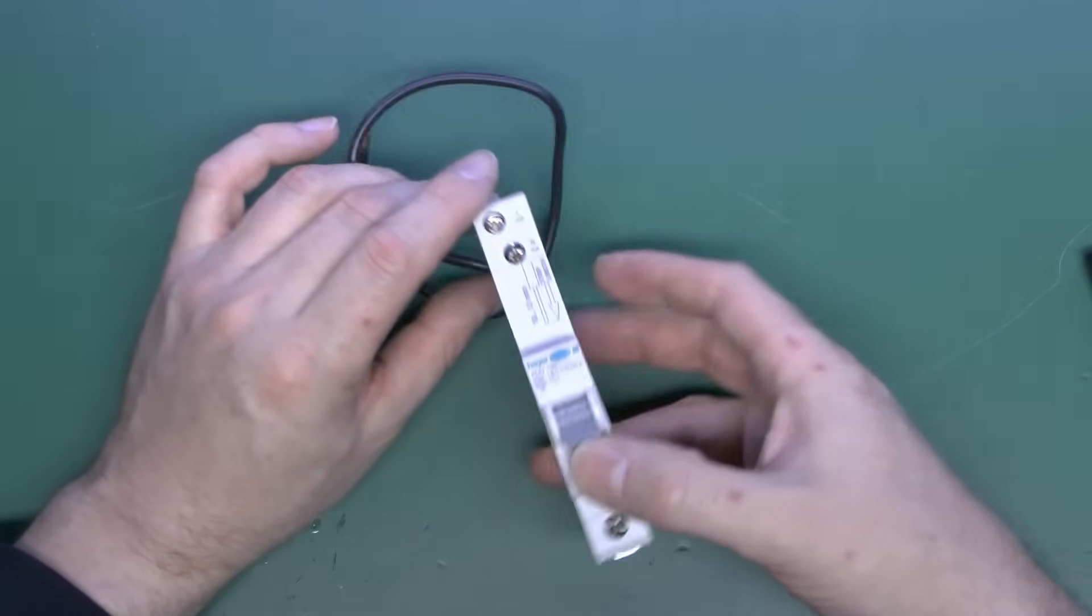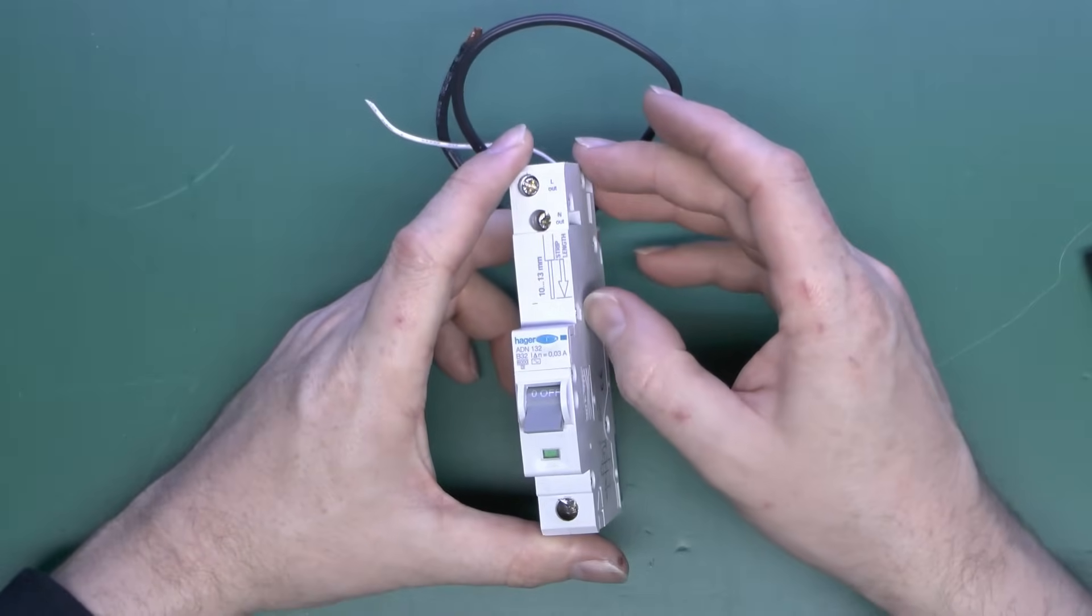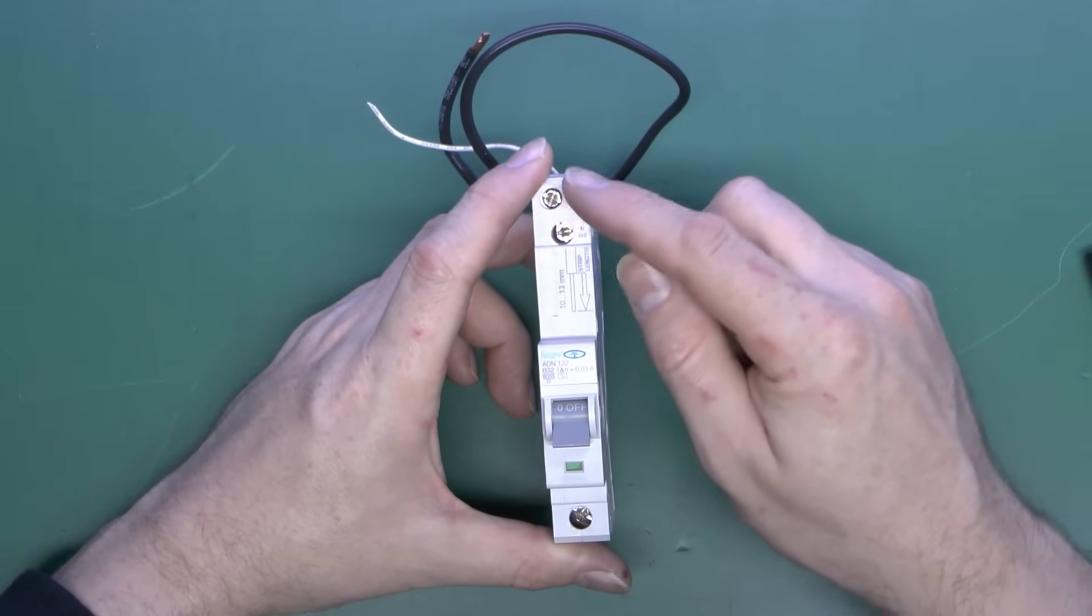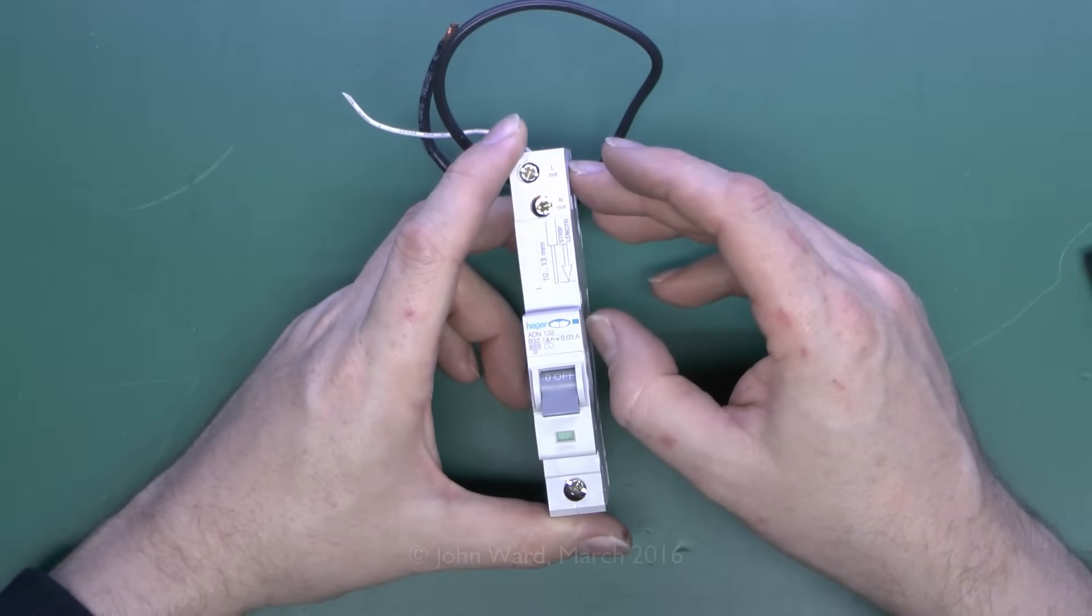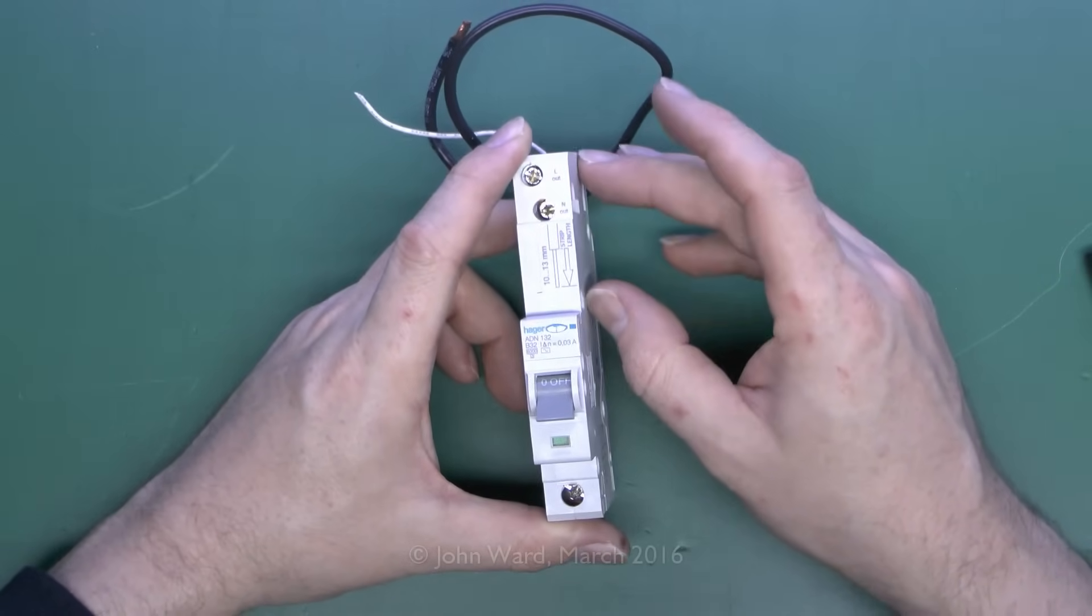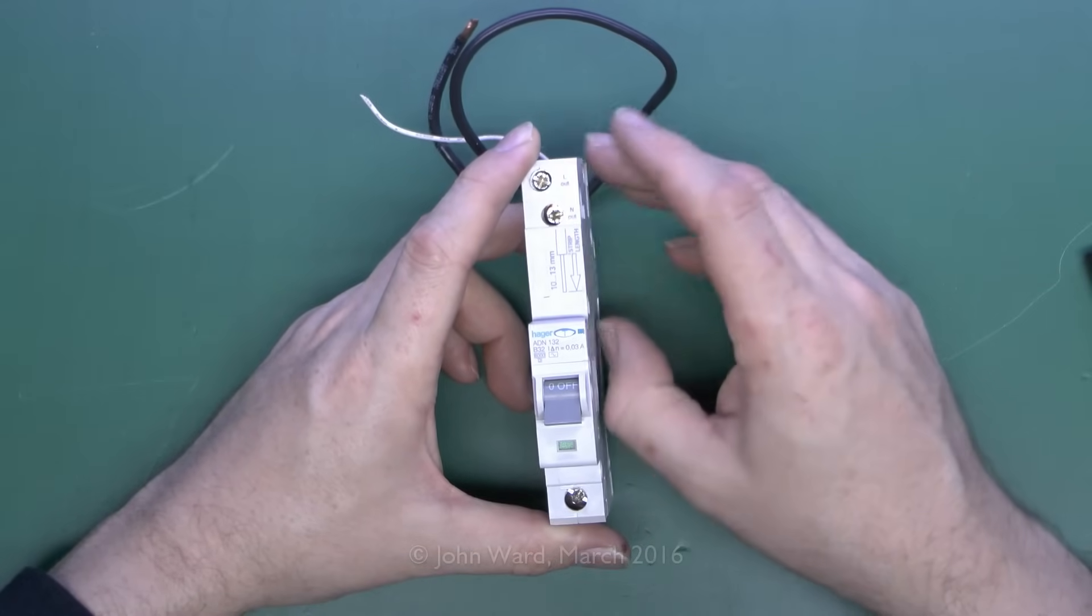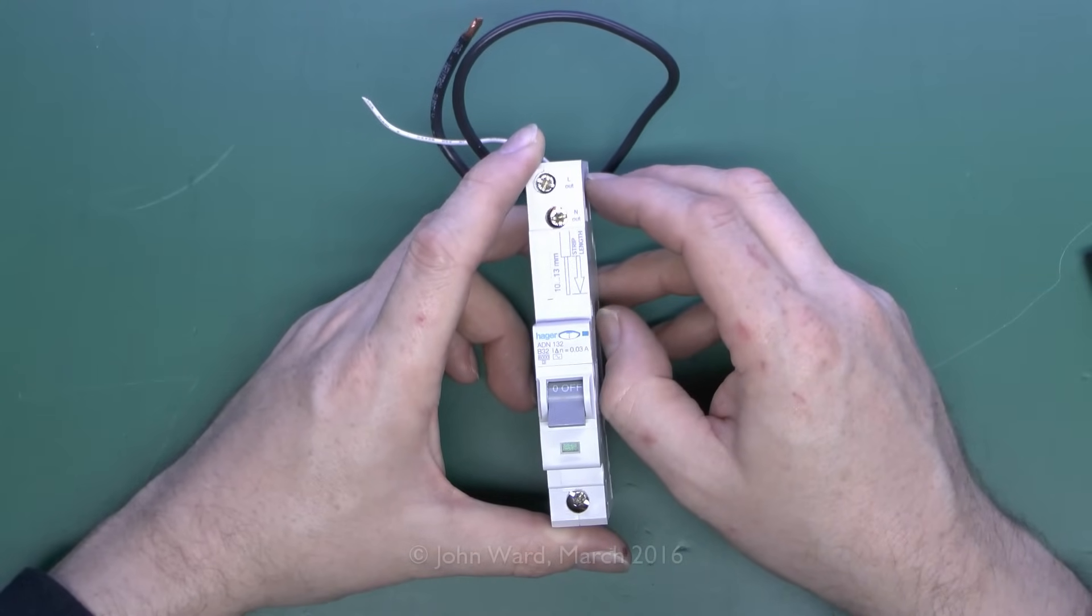And it's got the RCD functionality built into the top, and that's the part which monitors the current on the line and the neutral, and then will trip the device if there's any imbalance detected, and in this case an imbalance of 30 mA or more.